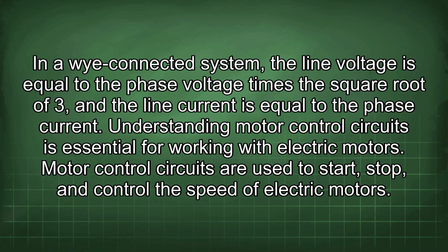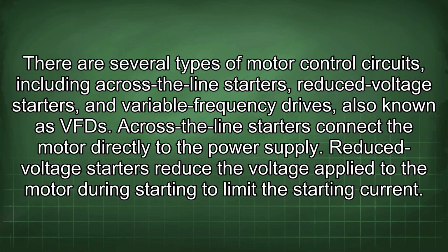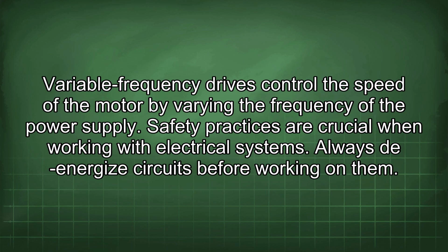Understanding motor control circuits is essential for working with electric motors. Motor control circuits are used to start, stop, and control the speed of electric motors. There are several types of motor control circuits, including across-the-line starters, reduced voltage starters, and variable frequency drives, also known as VFD. Across-the-line starters connect the motor directly to the power supply. Reduced voltage starters reduce the voltage applied to the motor during starting to limit the starting current. Variable frequency drives control the speed of the motor by varying the frequency of the power supply.